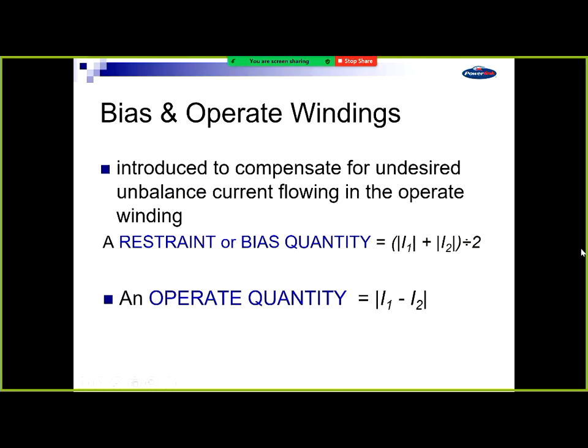So we introduce this bias or operate winding for undesirable unbalances: CT errors and transformer mismatches that happen. The restraint quantity is given as the absolute value of I1 plus I2, divided by 2, and the operate quantity is just those two subtracted. That's the typical old electromechanical standard way of doing things.